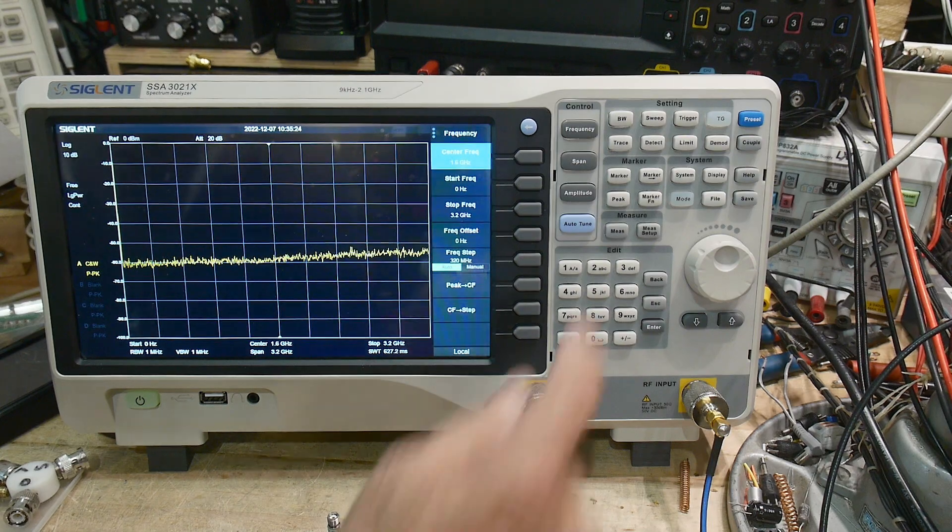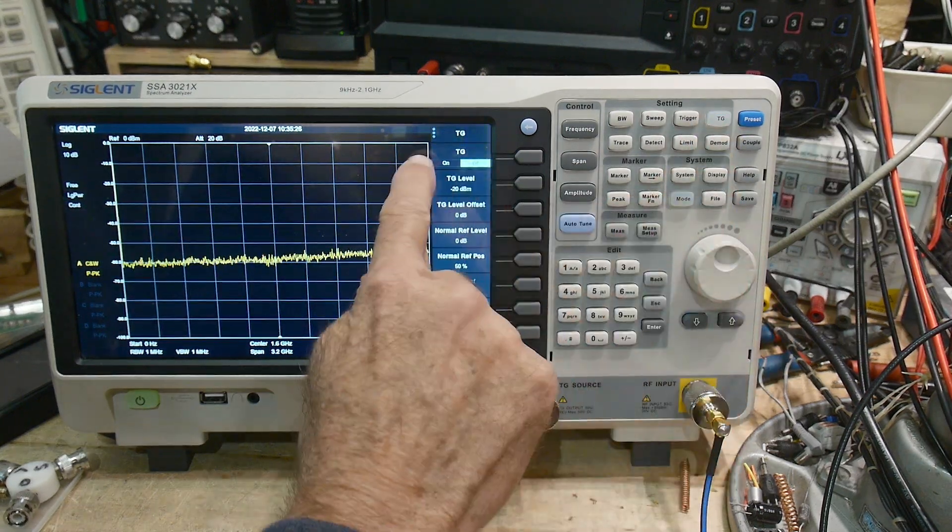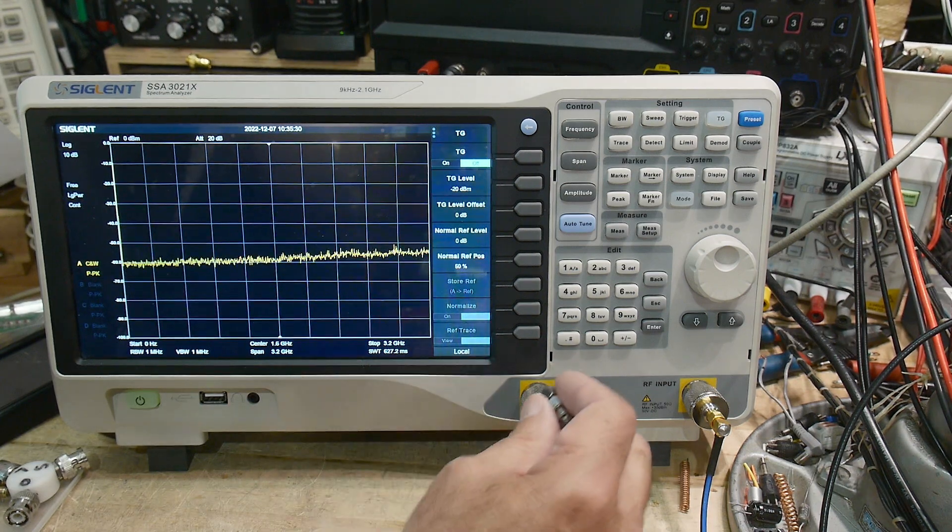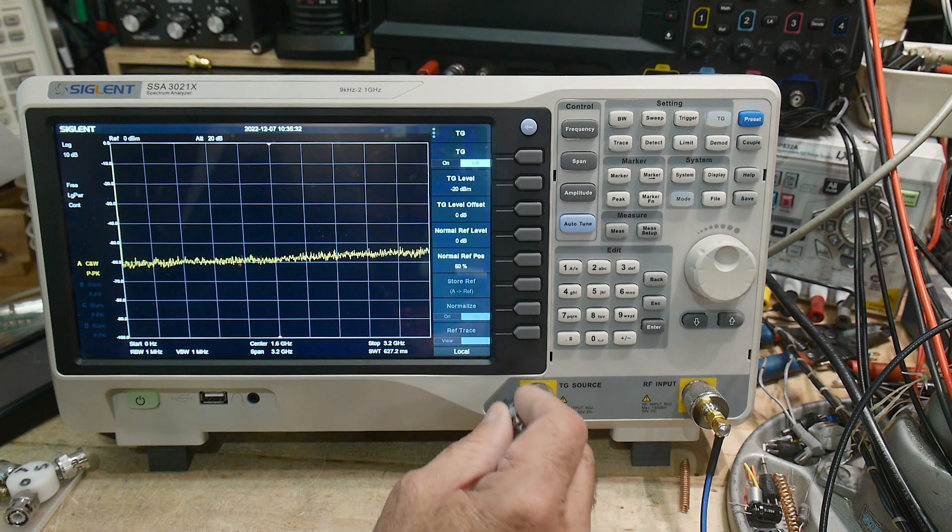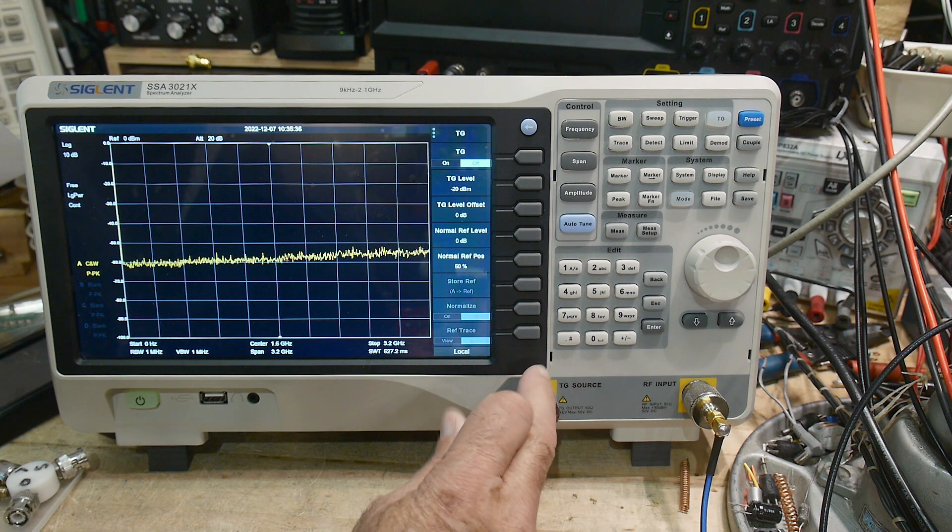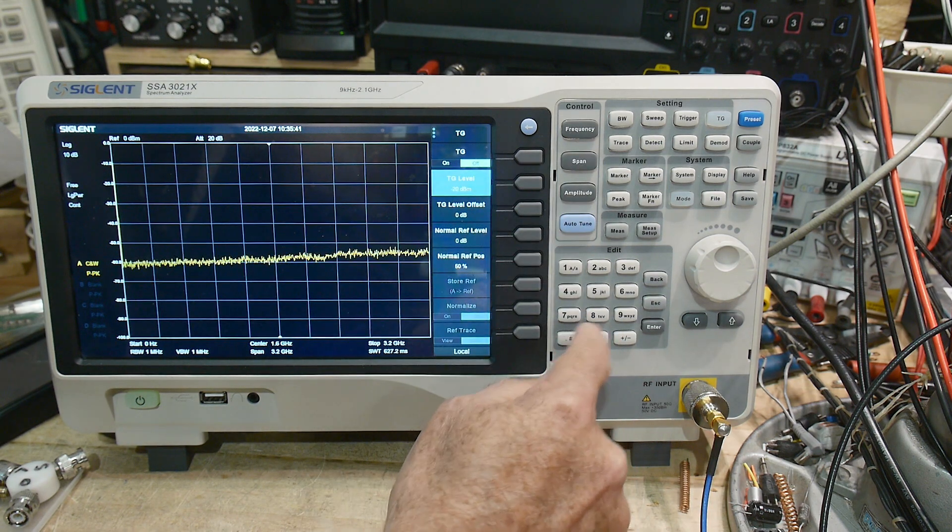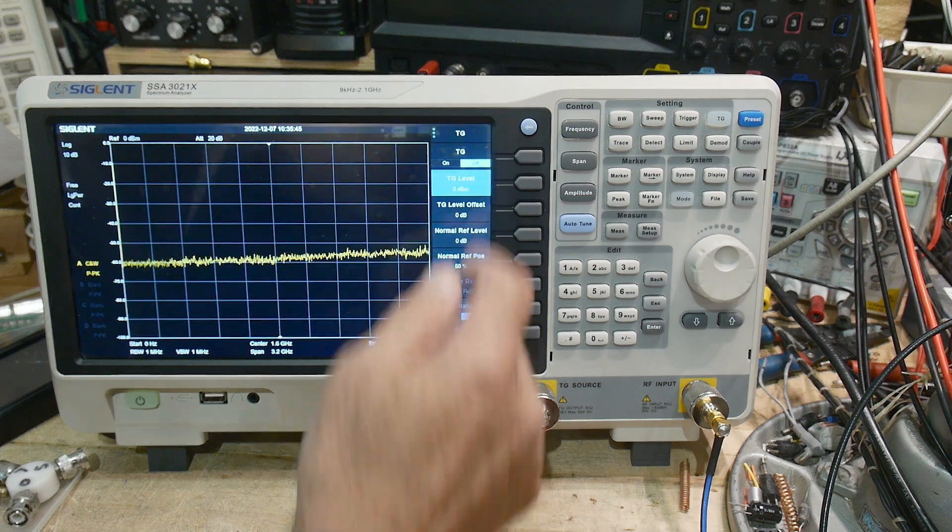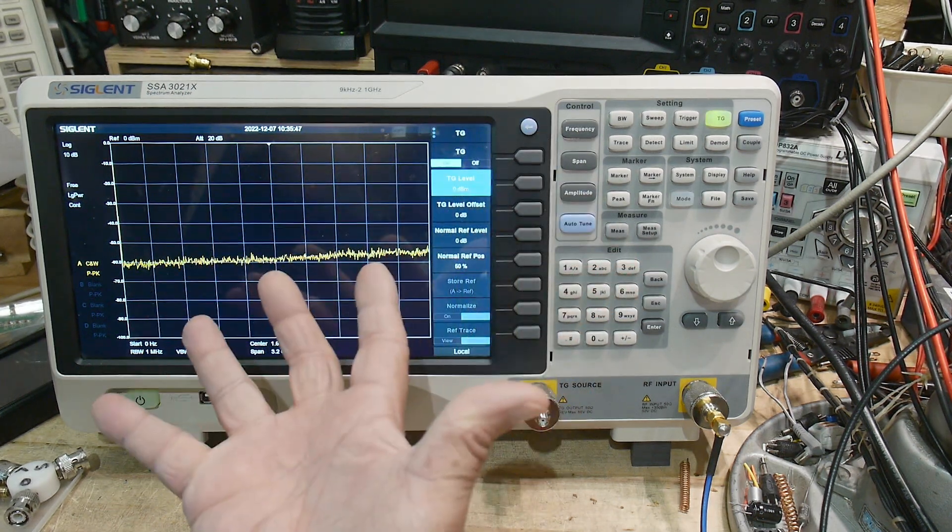Then we need to turn on the tracking generator, which is here. It says tracking generator on/off. You need to set a level. Now we're going to be testing attenuators, so we want a fairly high level out of the source because we're going to be attenuating it before we measure it. So let's go ahead and set the output to 0 dBm. We can say tracking generator on.